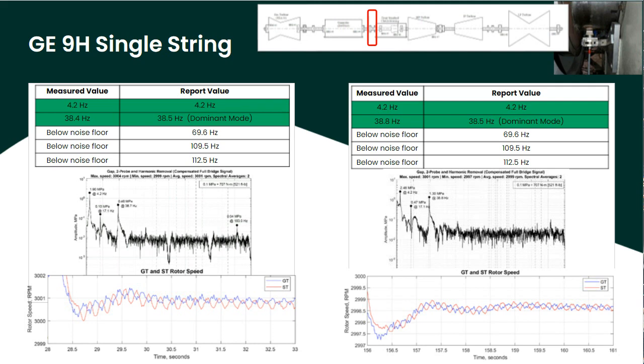There's good agreement between the measured and report values, indicating the machine is operating as expected. The torsional vibration response at 4.2 Hz had enough amplitude that it could be seen in the rotor RPM plot shown in the bottom. In this plot, the blue line is the gas turbine speed and the red line is the steam turbine speed. In this mode, the gas turbine is 180 degrees out of phase with the steam turbine.